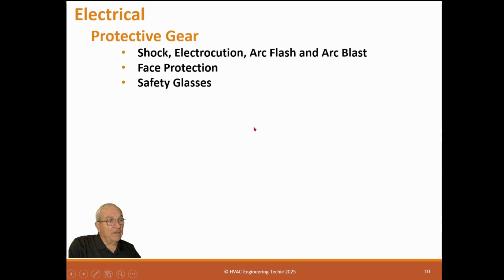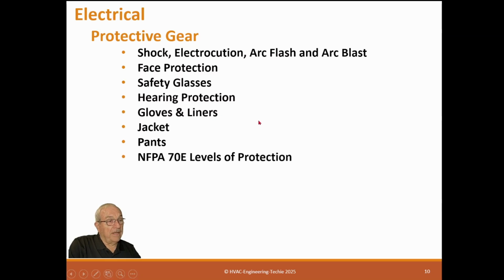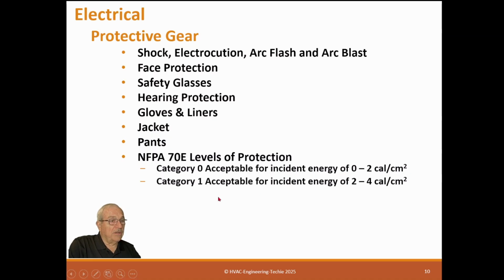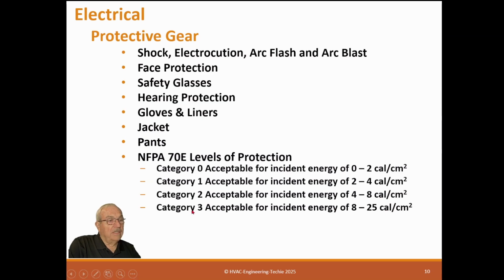Face protection, safety glasses, hearing protection, gloves and liners, jackets, pants, and NFPA 70E levels of protection, and we'll go through what those are. Category 0 is acceptable for incidents of 0 to 2 calories per centimeter squared. Category 1 is for incidents of 2 to 4 calories per centimeter squared. Category 2 is an incident of 4 to 8 calories per centimeter. Category 3 is acceptable for incidents of 8 to 25 calories per centimeter. Category 4 is 25 to 45 calories per centimeter.